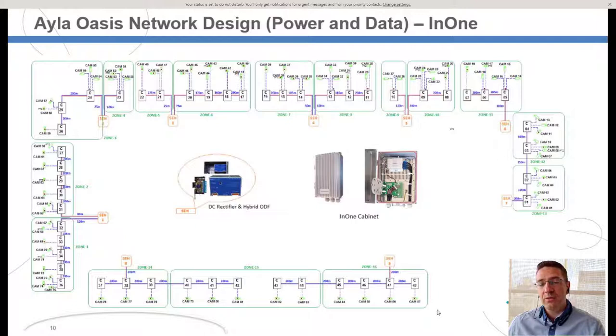When we told them we could do it with only 9 AC power locations, they were really surprised. We explained the solution and they were convinced to go with this design. It's been implemented and working now for 6-7 months, and alhamdulillah we've had no faults or issues at all. In this design, as mentioned, we distributed the rectifiers across 9 locations, with each rectifier serving several zones.